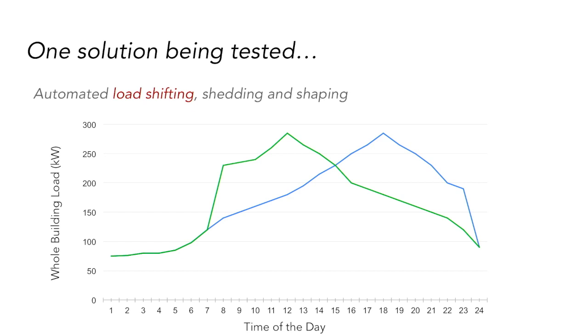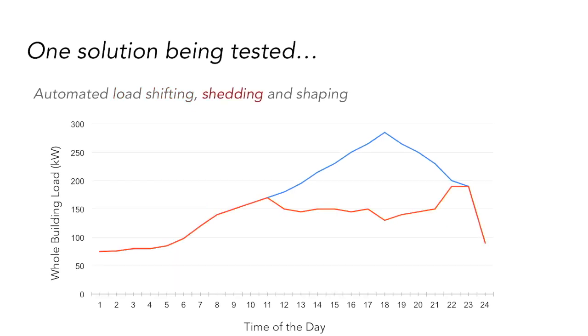Shedding is a bit different because now we're not only saving energy, but also reducing the peak. A typical strategy: if you're operating your building at 72 degrees, you increase that set point to 74. Now your chillers back off, your fans back off, and you can actually save energy for a period of time.